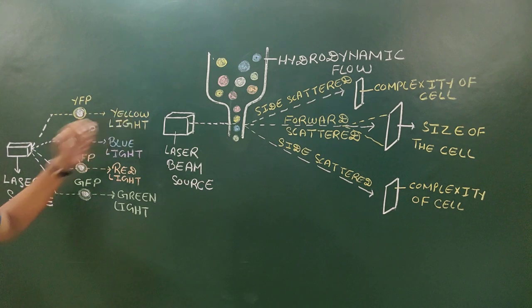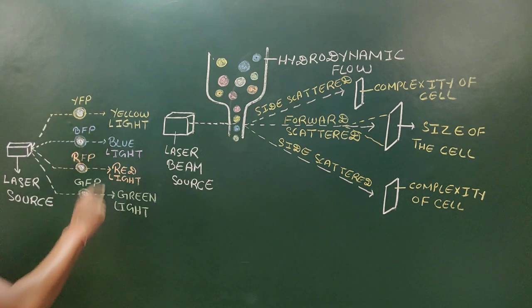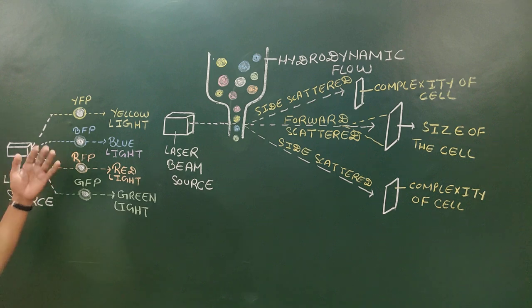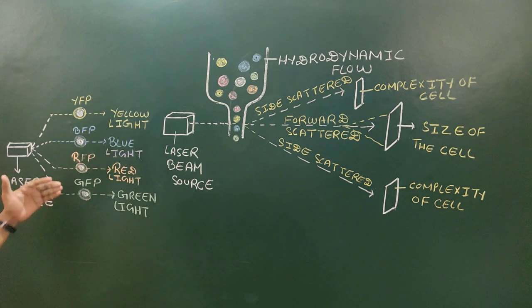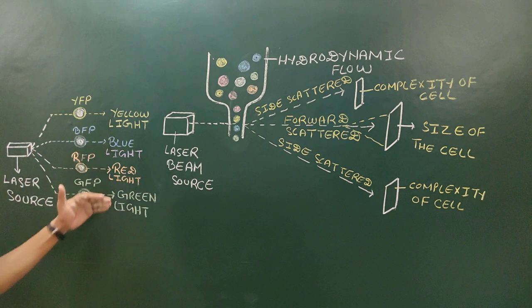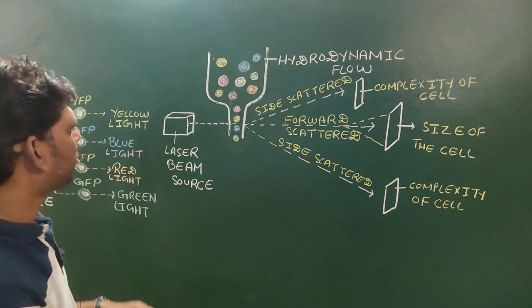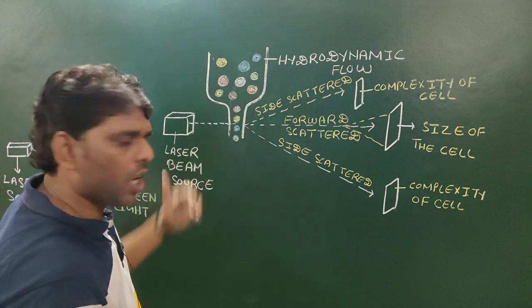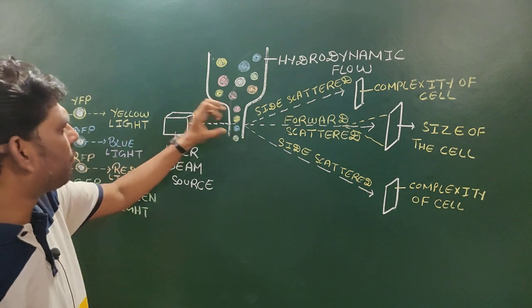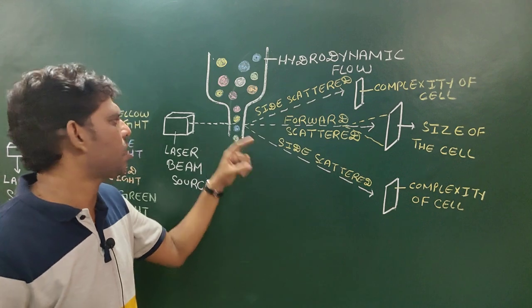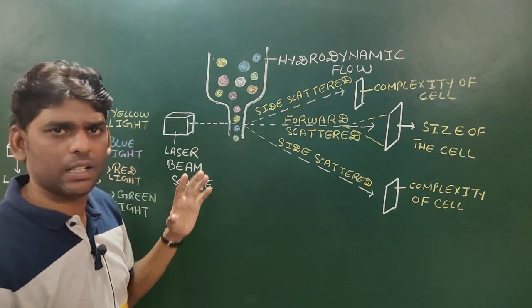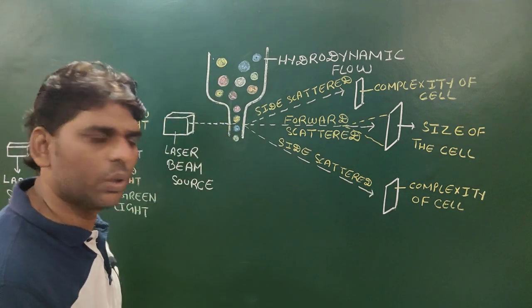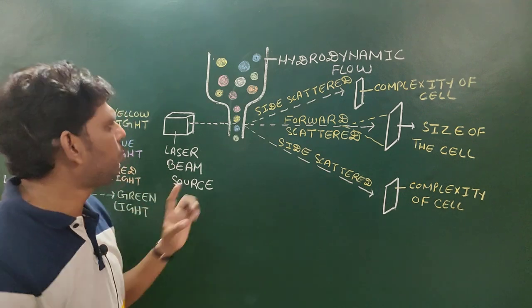When these cells tagged with different fluorescent proteins interact with the laser beam, they get excited and emit different kinds of fluorescent light. The cell tagged with yellow fluorescent protein emits yellow light, the cell with blue fluorescent protein emits blue light, the cell with red emits red light, and the cell with green emits green light. By using hydrodynamic flow, cells come through the column and when they interact with the laser beam, the emission of different kinds of fluorescent light is an indicator of different types of cells. If four types of fluorescent light are emitted, it means the cell mixture contains four types of cells.